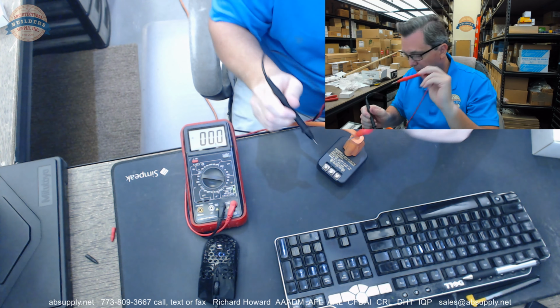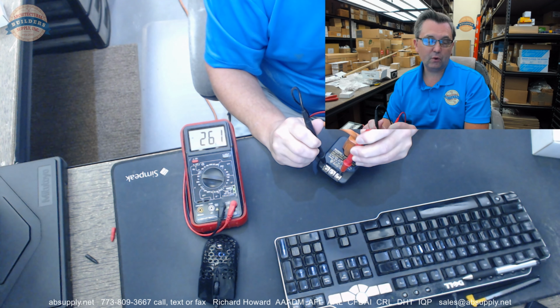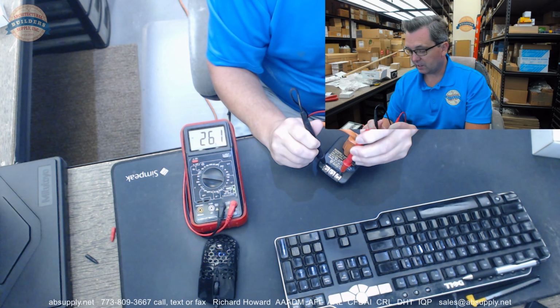So 3 and 4 are giving us 17.1 volts, so I'm going to say that's the 16 volt. Again, we're looking for 8, 16, or 24 volt AC. I'm going to keep my probe down on 3, then go to number 5. That's giving me 26 volts. So right now we've got 17 and 26.